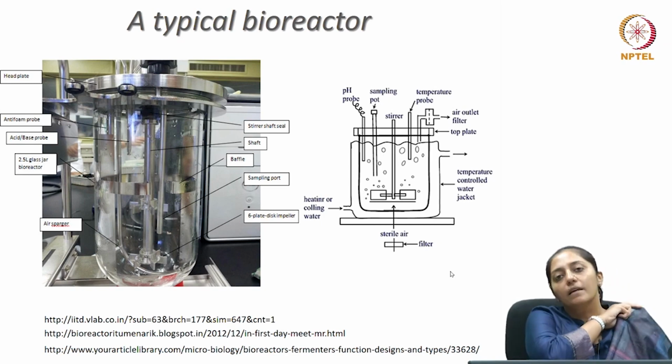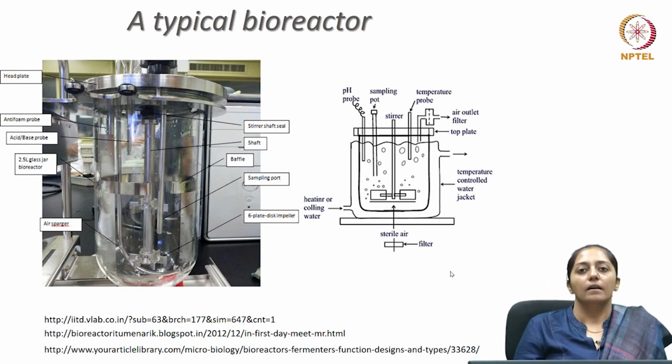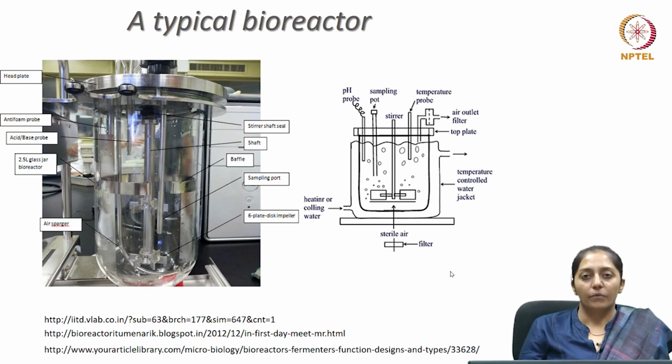Then from the head plate, you will see the measuring system, where you will have a pH probe attachment, a temperature probe attachment and an anti-foam probe attachment. The foam probe is capacitor based, the pH probe is generally polarographic or galvanic, and your temperature probe is based on the principle of a thermocouple. So, these are some of the crucial and major parts of the reactor.